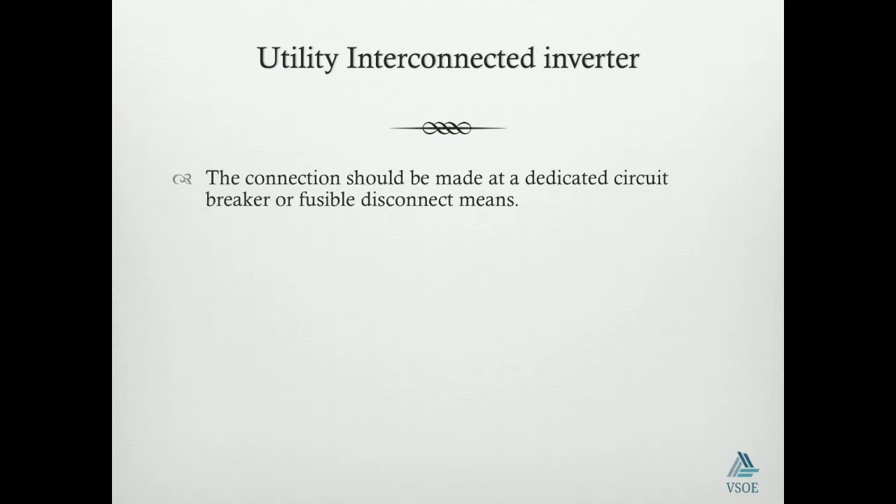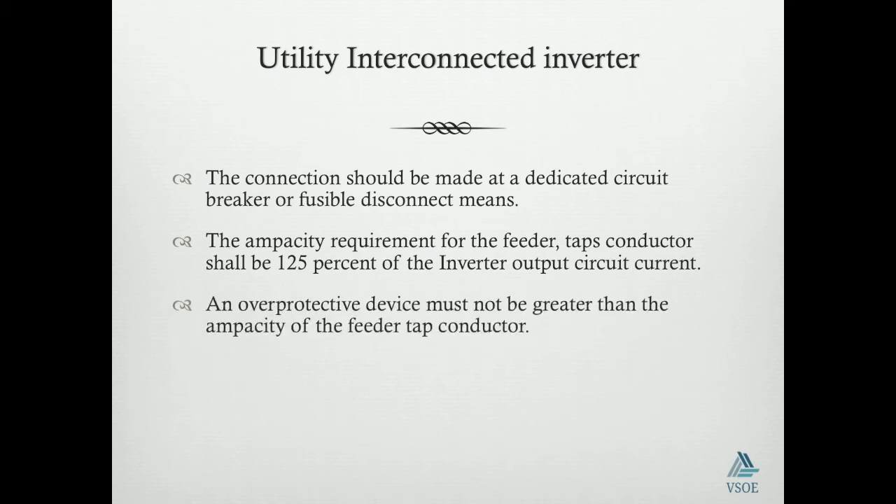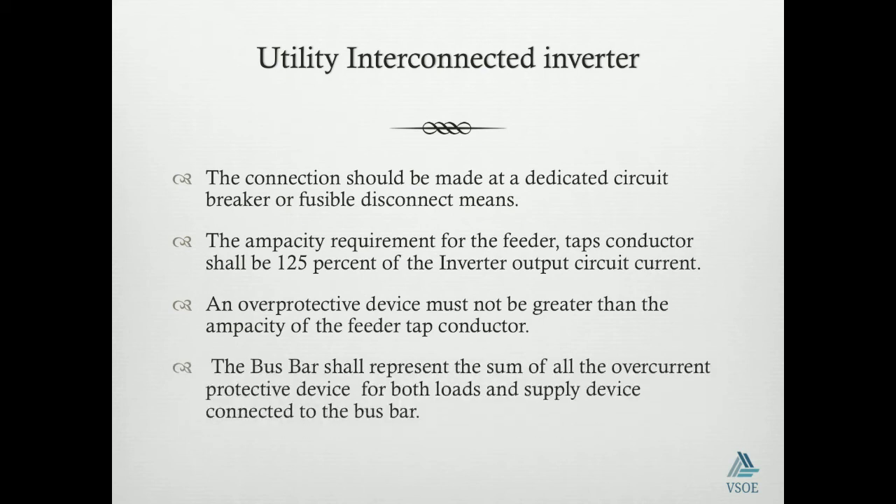The utility interconnected inverter connection should be made at a dedicated circuit breaker or fusible disconnect means to provide protection for the source. The capacity requirement for the feeder or the tap conductor shall be 125% of the inverter output circuit current. The feeder tap should be sized at a value much greater than what is delivered from the inverter output circuit. An overcurrent protective device must not be greater than the ampacity of the tap. The bus bar shall represent the sum of all overcurrent protective devices for both the load and the supply devices coming to the bus bar, so all taps or feeders coming to the bus bar should be equal to the magnitude of the ampacity of the bus bar.